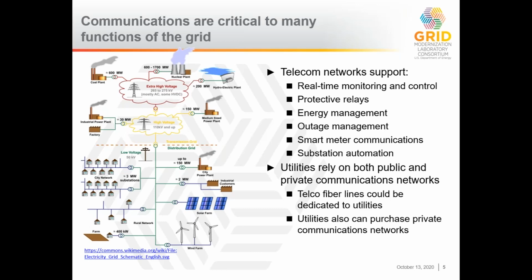When we get into distribution and expand this a little to focus more on the communication system, the type of communication depends on the type of function you're actually looking for. But on a very basic level, we tend to separate protection from metering. If there's a type of measurement that's meant to take an action locally, like protective relays would take, you'll focus on sending that data within the controlled boundary needed for protection. But when you're talking about things like smart meter communications, you want those to go up to the higher level and billing to be sent back to the right people. So we tend to separate those protection networks from the other networks used in the system.